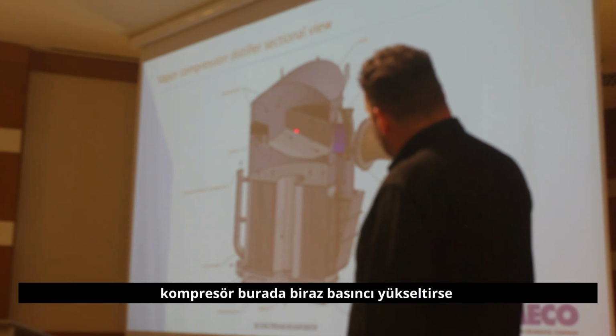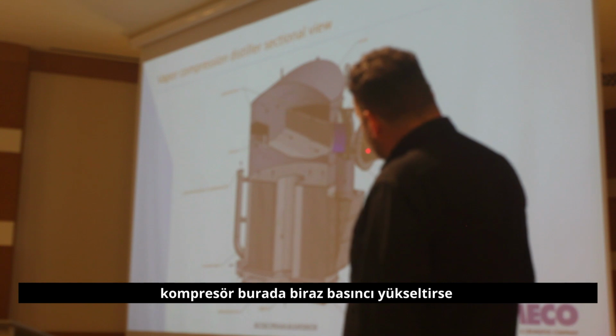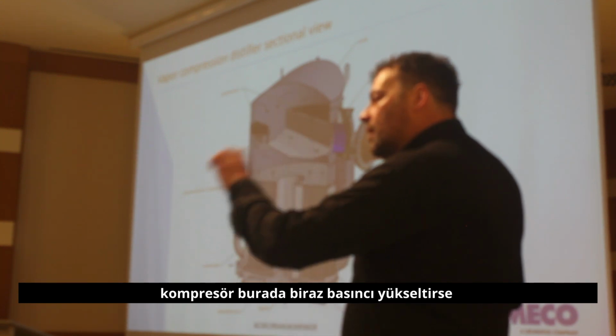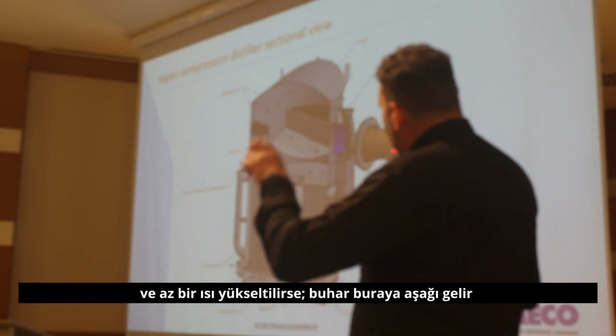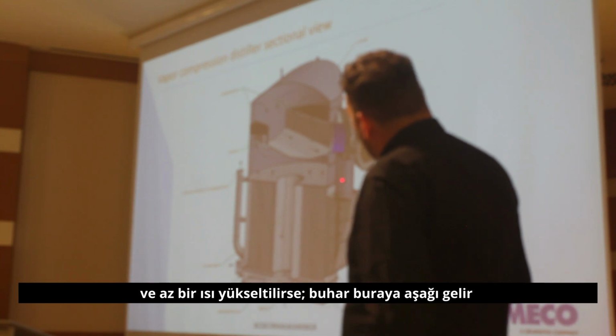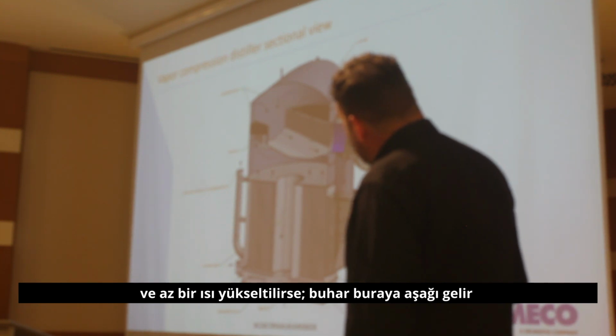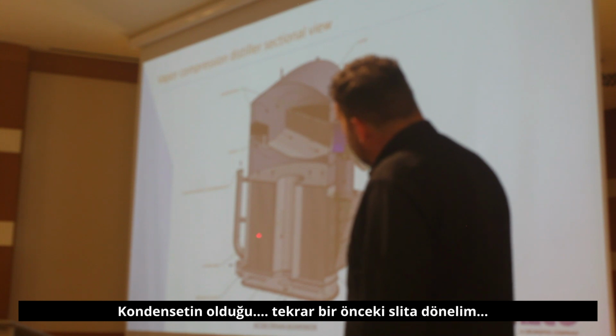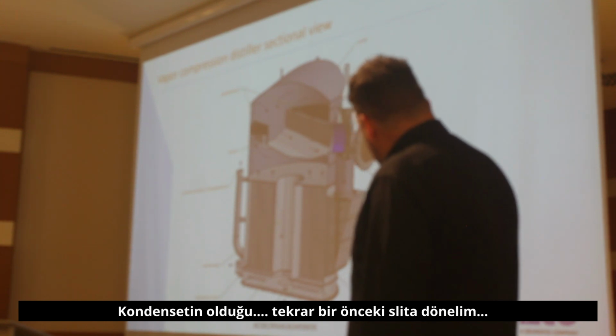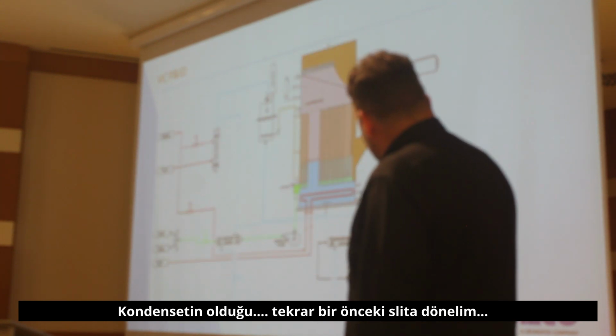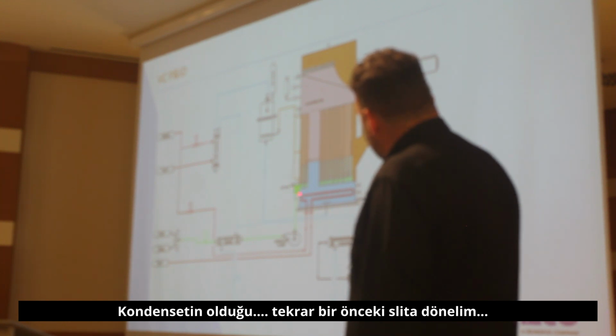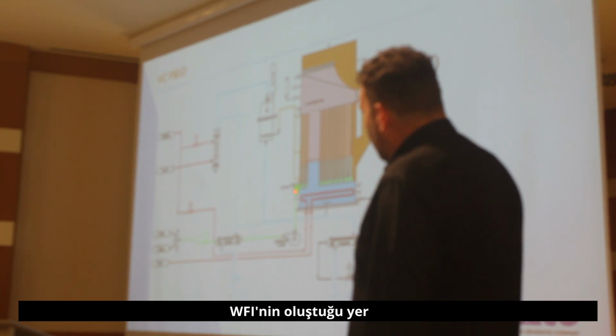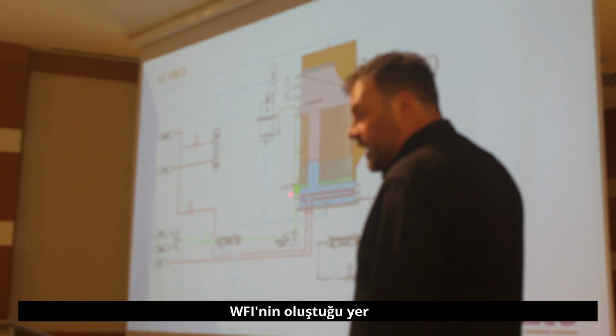Inside here, it then comes over here where the compressor is only adding a small amount of pressure and a small amount of temperature increase, and the water, the steam vapor comes down here again, where it condensates in the, and I'm going back a slide, the WFI outlet here. That is where it becomes water for injection.